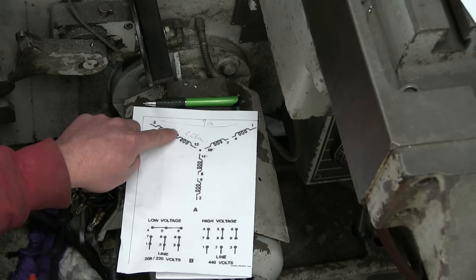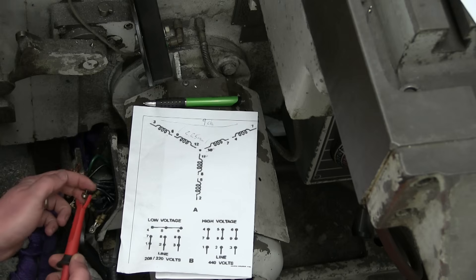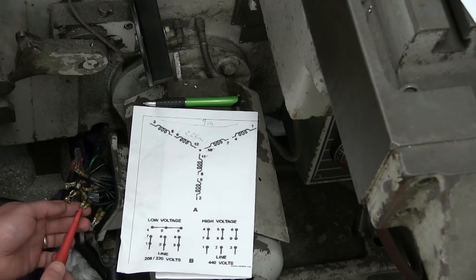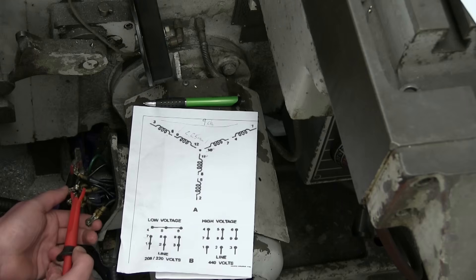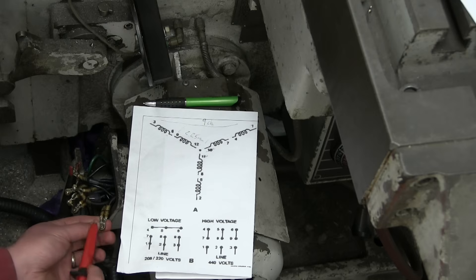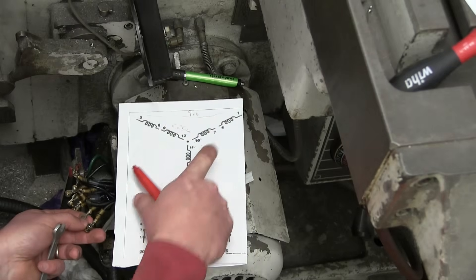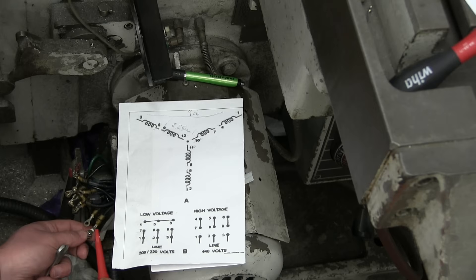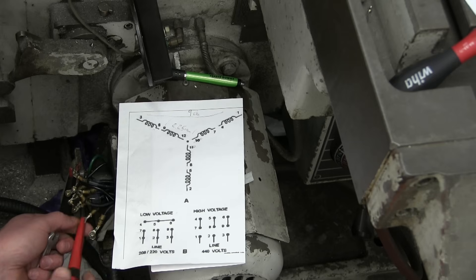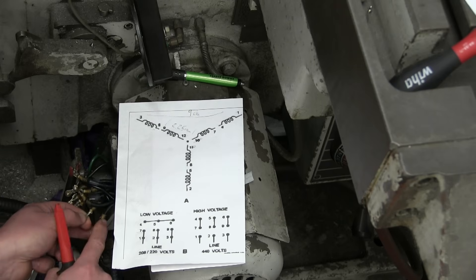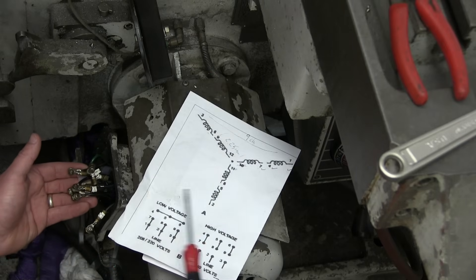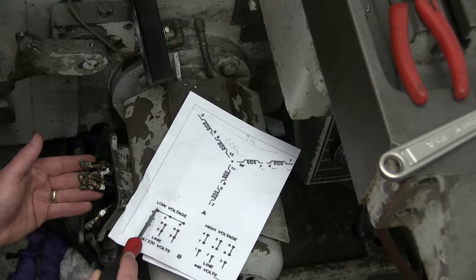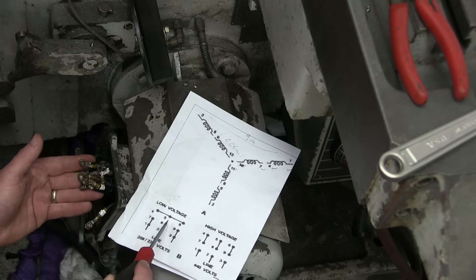Now for four and seven, we got our clamp on the one. If we find this guy, we know there's only one inductor here, so that's going to be 2.25 ohms. Everything else is going to be something like six ohms because we're checking all of these, so that'll be one, two, three, so it'll be six ohms. Let's have a look here. Okay, so we got 6.7 ohms, we got 2.3 ohms. That's the guy there. Double check, 6.6 ohms. So we know this connection is four and seven. Now which is which? Which is four and which is seven? What we do is we disconnect them here. Four will have continuity there, it should be 2.25, and seven will be open circuit. So that's open circuit, that means this one needs to be 2.4. Perfect. So we know that this guy is four, this guy is seven. Mark them. The hard part done. We hooped through the jumps, blanched our noodle to al dente. All we got to do is get a proper terminal block to connect four, five, and six together, and then seven, one, and the line in, and so forth.